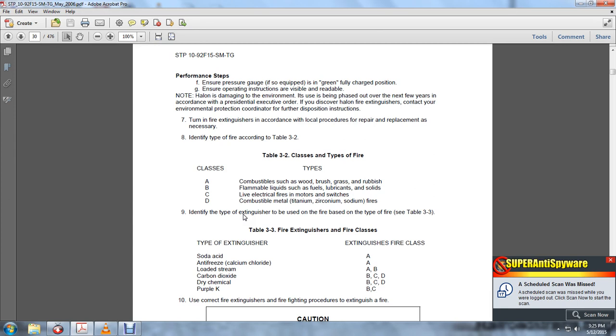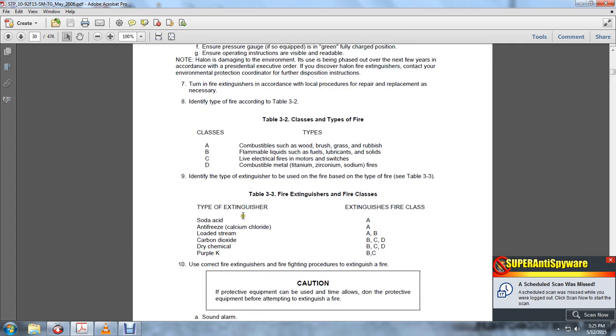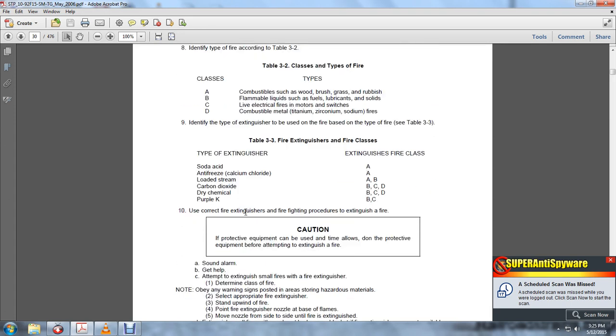Antifreeze or calcium chloride is class A. A loaded stream is A and B. Carbon dioxide is B and C. Dry chemical is A, B, C, and D. And purple K is B and C. Use the correct extinguisher and firefighting procedure to extinguish the fire.